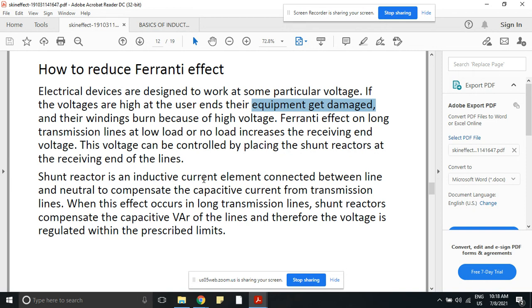That concept you have to keep it in mind. Shunt reactor is an inductive current element connected between line and neutral to compensate the capacitive current from transmission lines. So, when this effect occurs in long transmission lines, shunt reactors compensate the capacitive power of the lines, and therefore the voltage is regulated within the prescribed limits. So this is the overall concept of Ferranti effect. So once again I repeat, Ferranti effect is nothing but a phenomenon observed in case of long transmission lines in a considerable way, where the receiving end voltage will be greater than the sending end voltage. That is the first point.